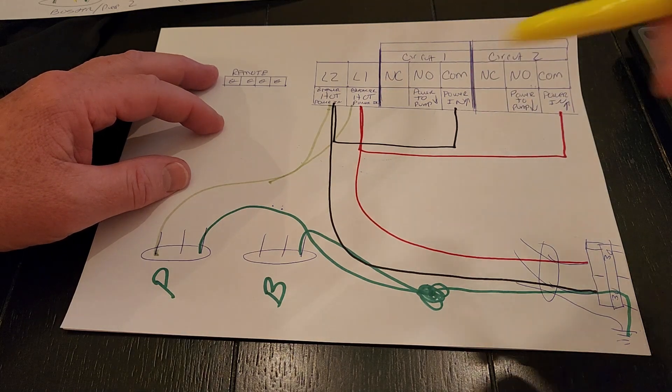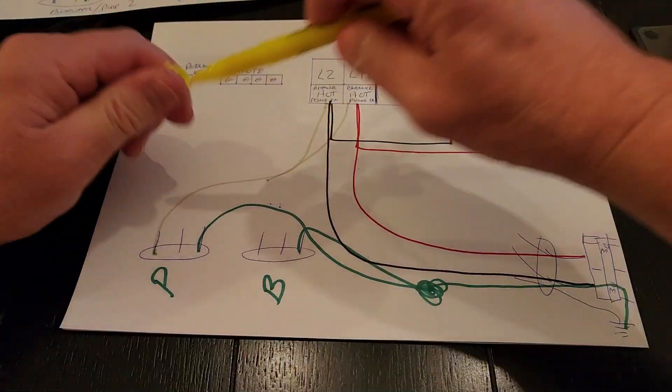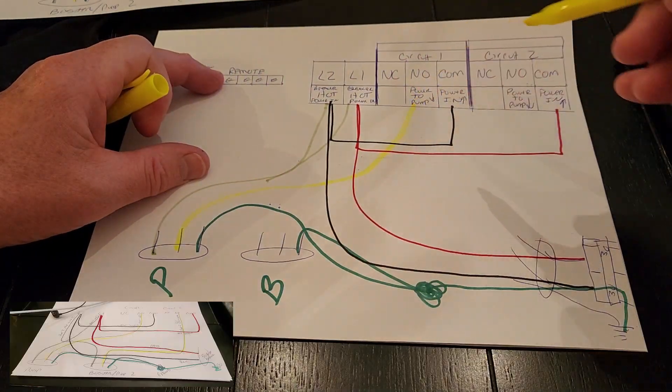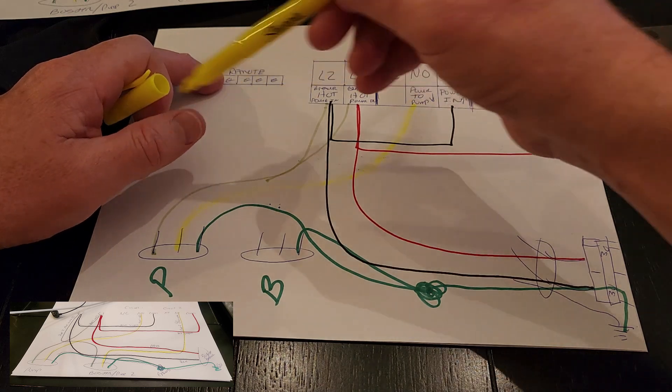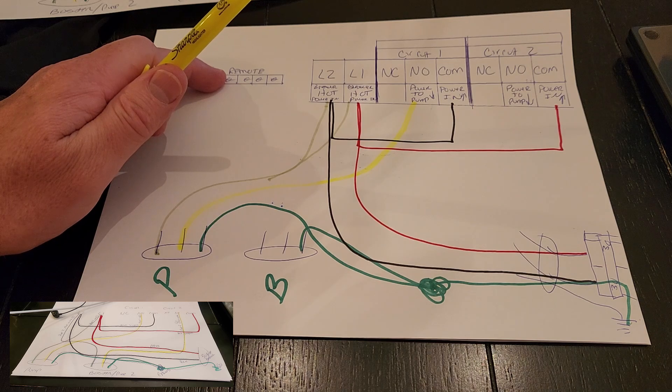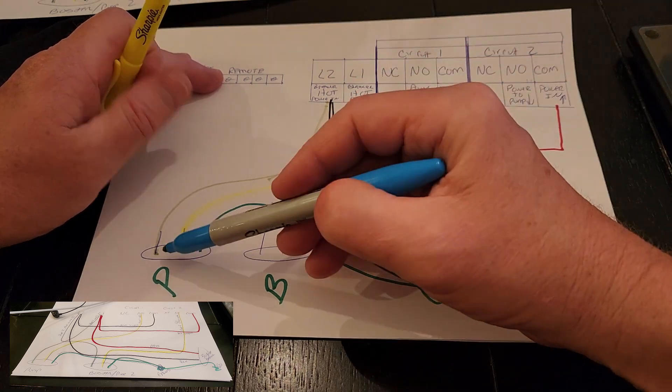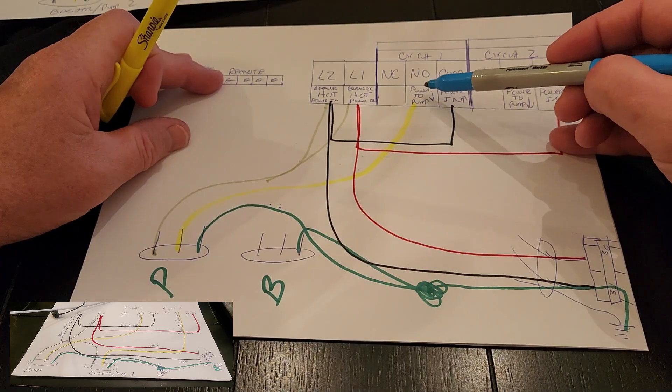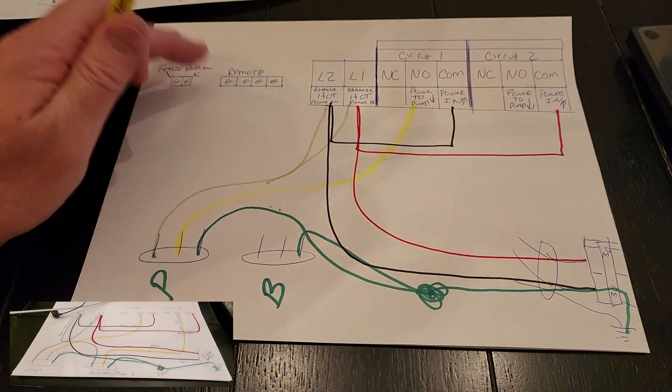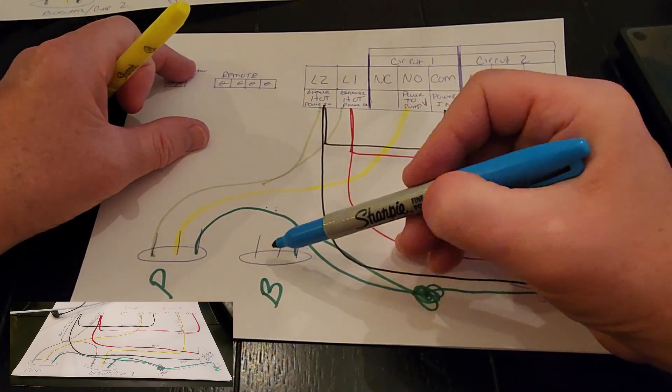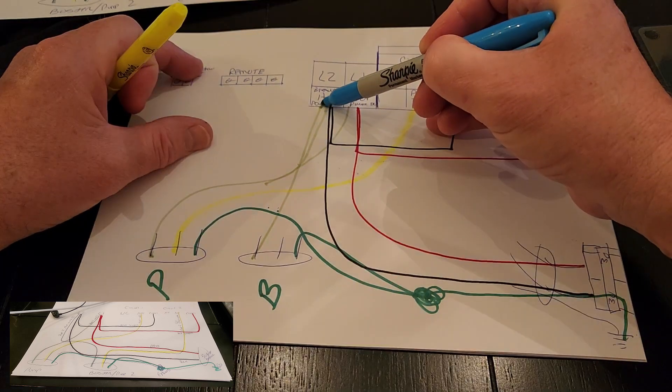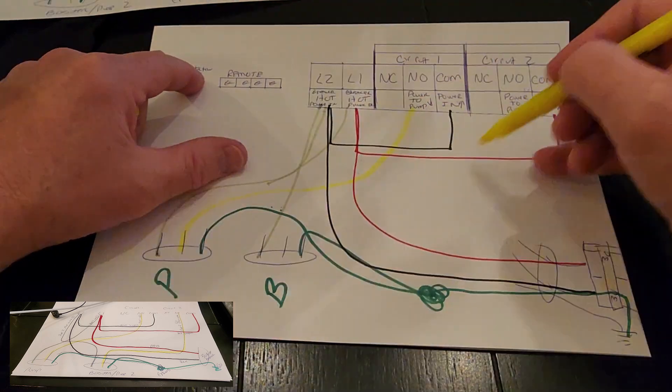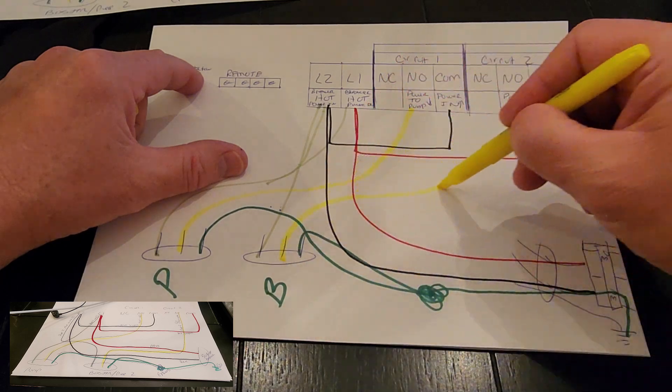And then we take, I hope this doesn't confuse you too much. So pool pump breaker goes into L1. Out power for circuit one goes into the other side of the main pool pump. So I'll give you a picture of the other schematic I drew because it's better, down below. So main pool pump goes into L1. Other side of the pool pump goes into circuit one. One wire of the other pump goes into L2. And the other wire of the other pump goes into circuit two. Normally open.